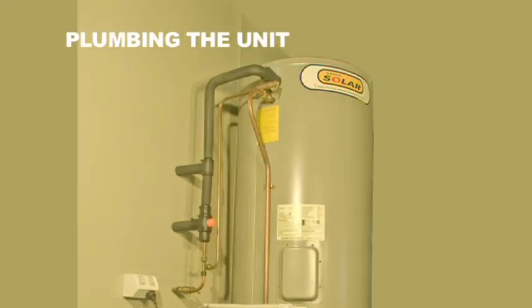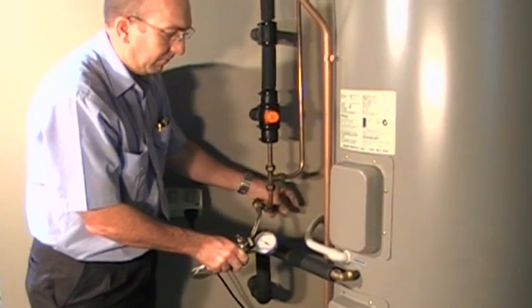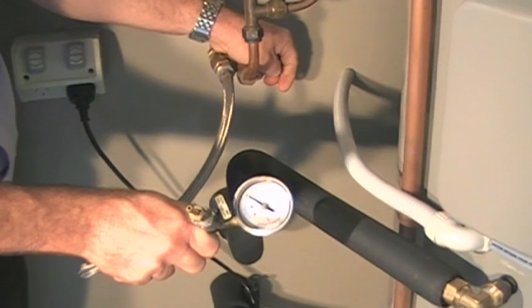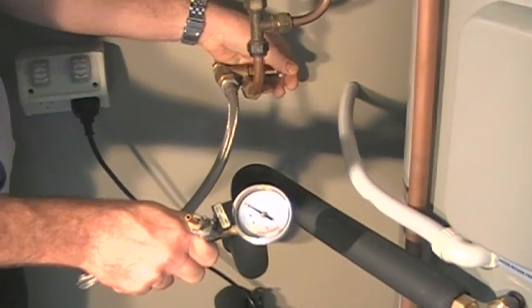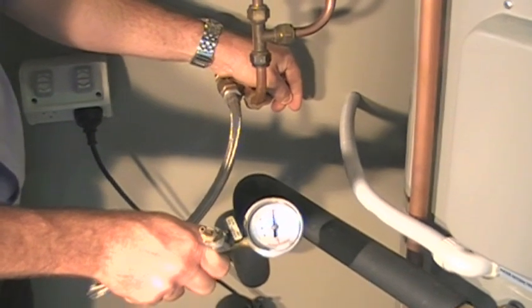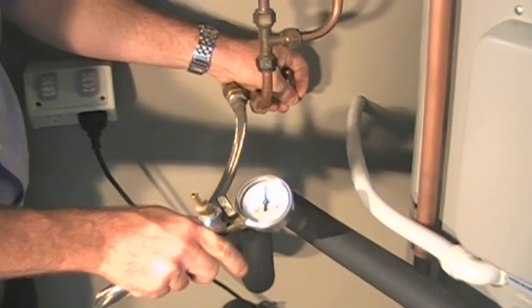The water heater is installed in exactly the same manner as Solar Heat Exchange Water Heaters. Check the mains pressure. If it is over 1100 kPa, connect a pressure limiting valve as required by law. If it is over 800 kPa, consider connecting a limiting valve as this may prevent the possibility of water hammer.